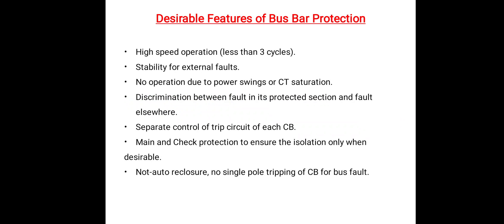What are the desirable features of a bus bar protection scheme or bus bar protective device? The most important feature is high speed operation — the protective device must be capable of operating in less than 3 cycles. Stability for external faults means whenever the fault occurs outside the protective zone, our system must remain stable. No operation due to power swings or current transformer saturation — when the iron core of a CT is saturated at high current, the protective scheme must not operate at that particular instant.